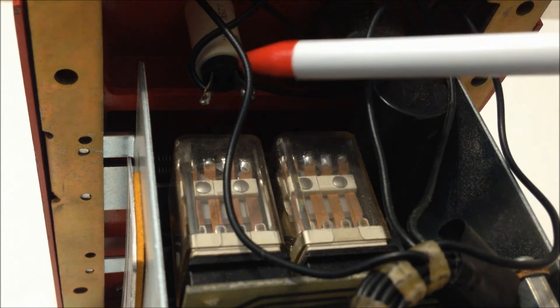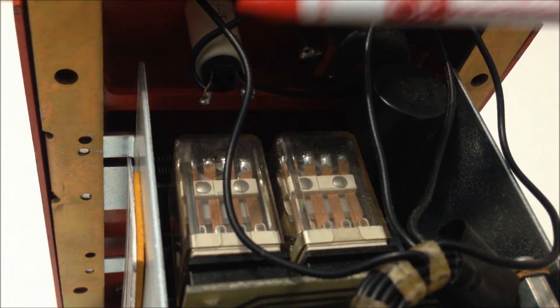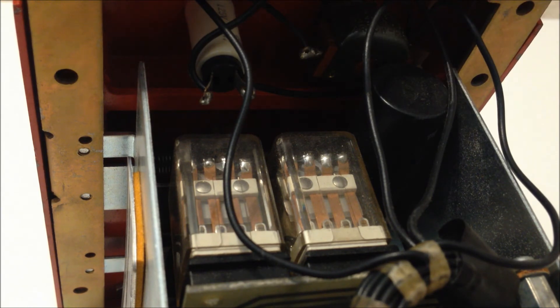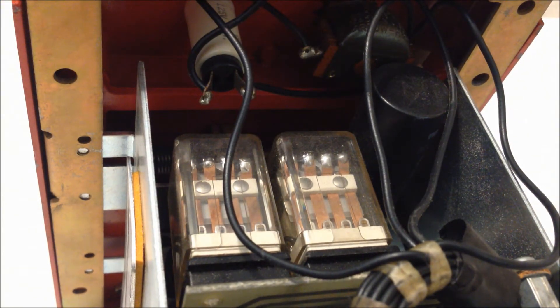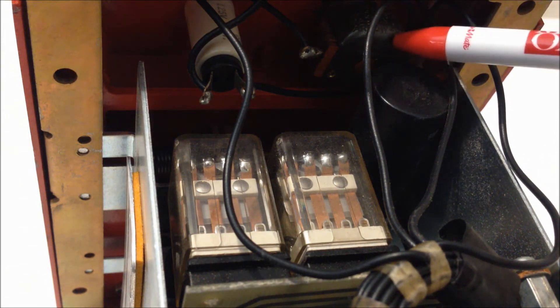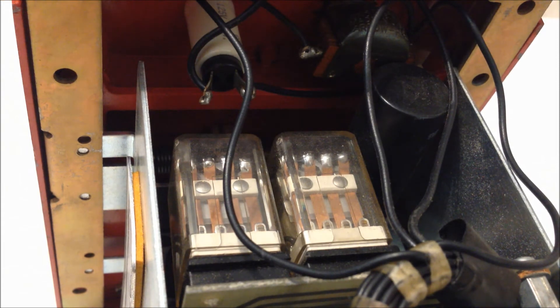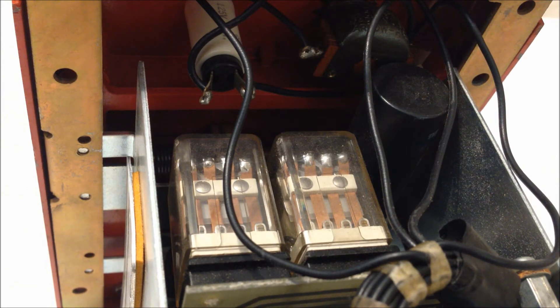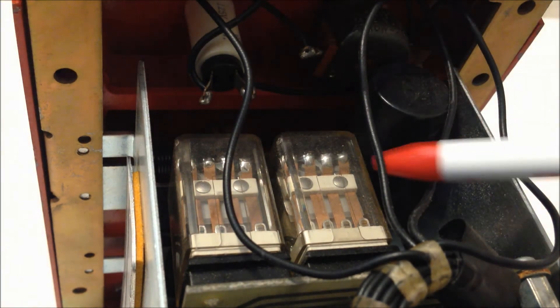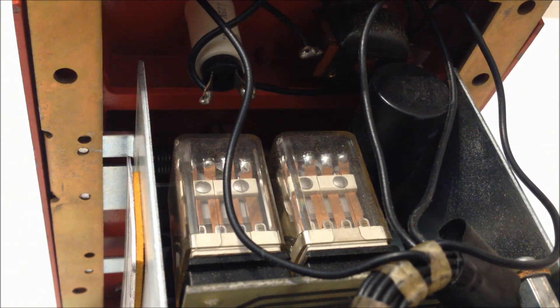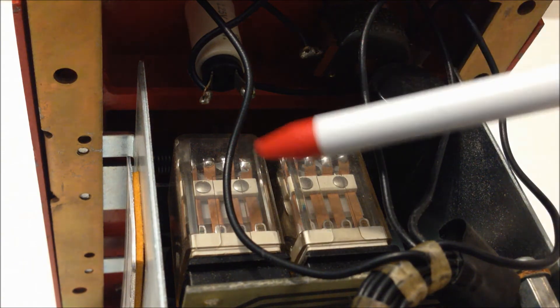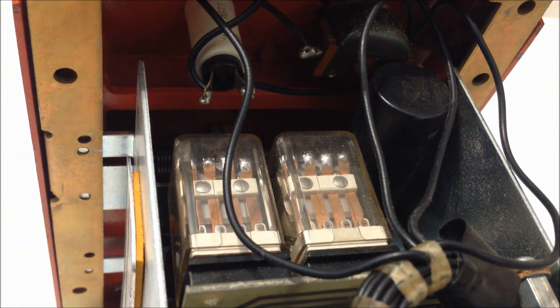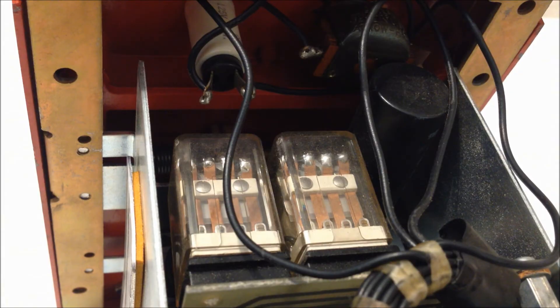Right here is the back of the trouble light on the front. This is just a 120 volt incandescent bulb. And then over here, this is the switch on the front that's used for resetting the pull station. And that uses a Simplex A or a 424 key in order to operate. And these two devices, the light and the relay, are tied into one of these relays. And then the micro switch that actually runs the coding, I believe, is tied into another one of these relays. So what I'm going to do now is actually connect it to 120 volts and we're going to see this thing in action.